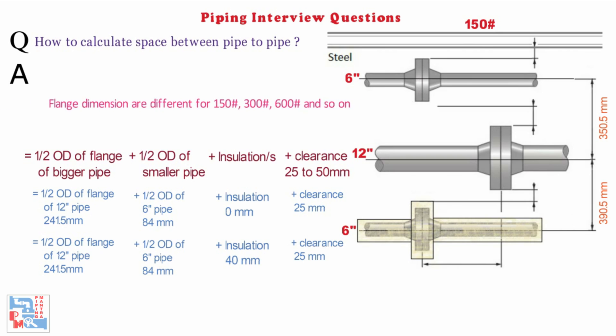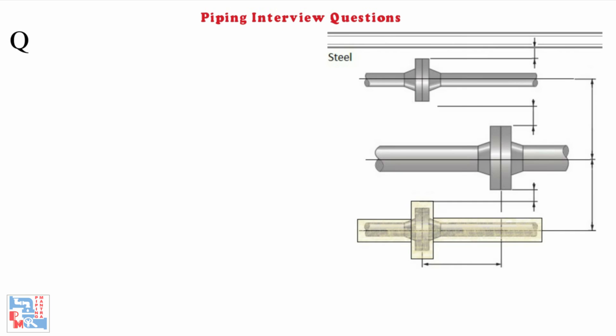Please remember, flange dimensions are different for 150 lb rating, 300 lb rating, 600 lb rating, and so on. If stress requires additional space for thermal movement, we need to provide this space as an addition. Next: How much clearance do we keep from steel to pipe? It should be 75 mm minimum from the outer edge of pipe or insulation.